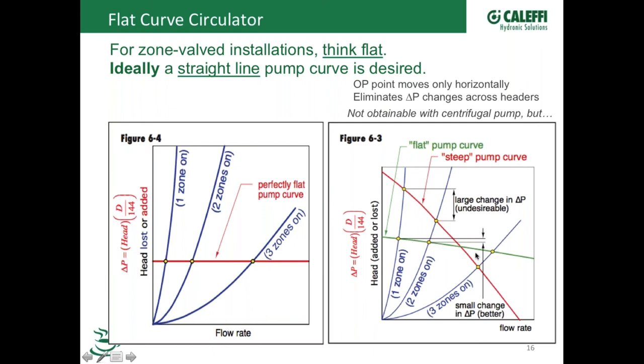green one here. So in this example, suppose you had a job, and we know the numbers here, and let's say you required 12 gallons a minute, and this was 12 gallons a minute there, and you ran up. Both of these pumps would actually work for that job, 12 gallons a minute at that operating point. So you say, well, should I use this pump here? Let's call that maybe a high head. I don't know, let's throw out a number like a 2699, or should I use this pump here, which is maybe a 1558? Well, if you're going to be zoning, you want this flat curve.